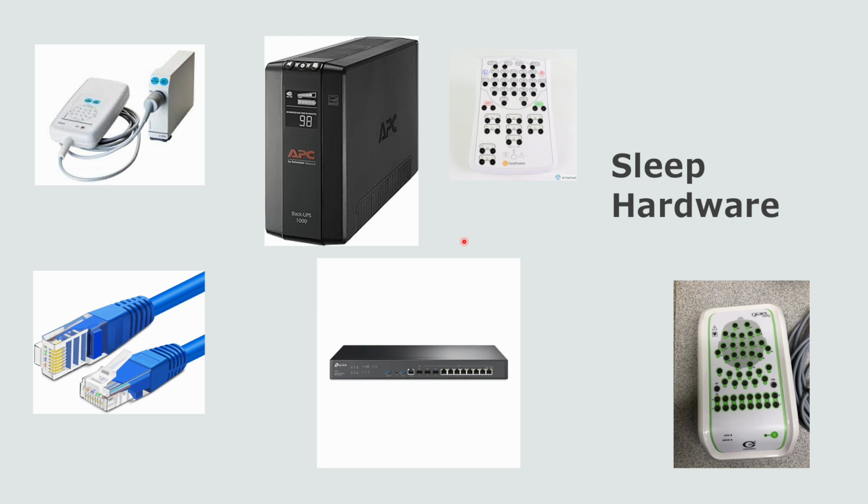There usually is a big white headbox looking thing, usually off to the side in the patient room, with a big long thick cable coming back that hooks up into the headbox. And this big white box is the amplifier. That's the machine that takes super small brain waves and makes them bigger, or amplifies them, so that we can see them.